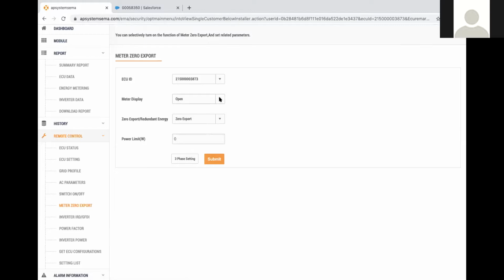You have the meter zero export here. You will have this function as an installer, and if you forgot to do it on site, or the regulation changes in Australia and suddenly you can export into the grid - meter display, that's when you have the CTs, you can turn it on or off. I see the curve, I don't see them - zero export, I don't want it anymore, I close it. And you can also do zero export using QS.